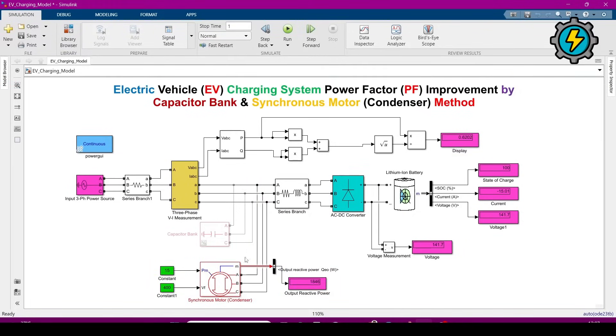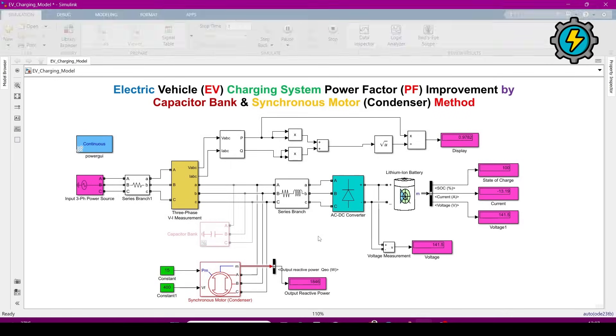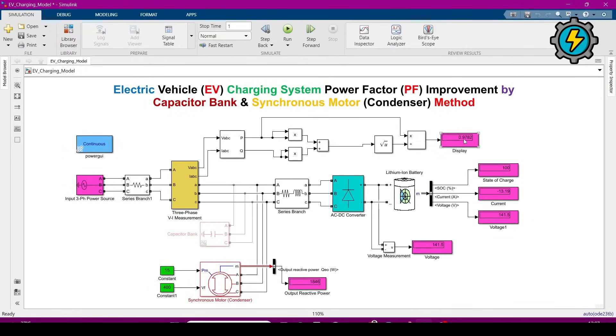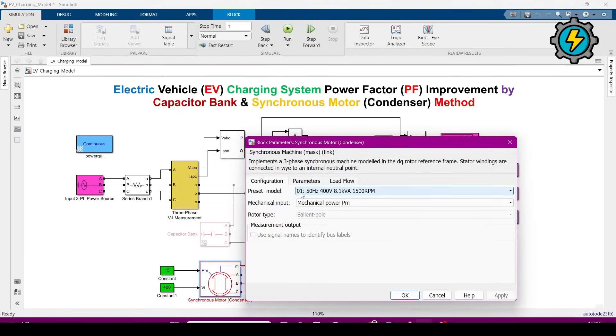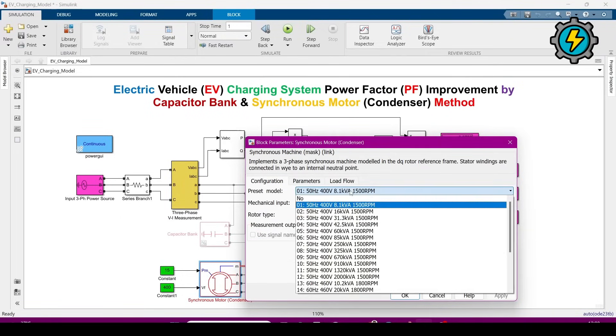I uncommented it and will run the simulation now. You can see the power factor is improved to 0.97. The reactive power supplied by the synchronous condenser is 1846 VAR. Looking inside its configuration by double-clicking, I am using 50 Hz, 400 V, 8.1 kVA, 1500 RPM. When you click on it you can also see other motor varieties.